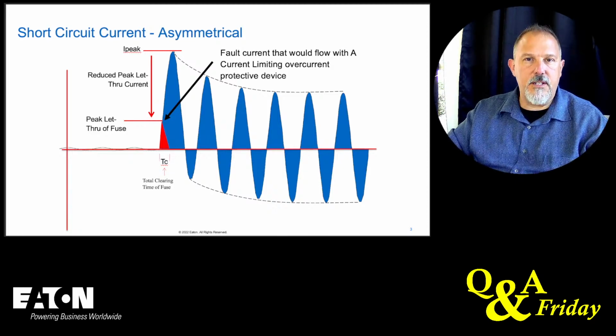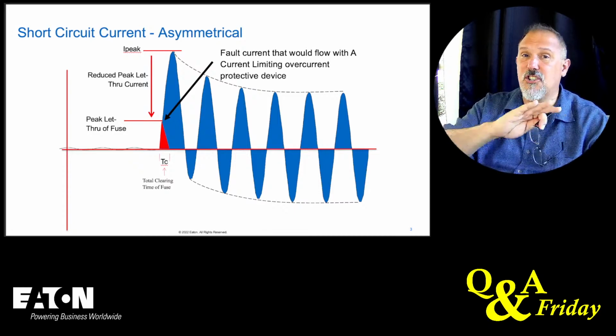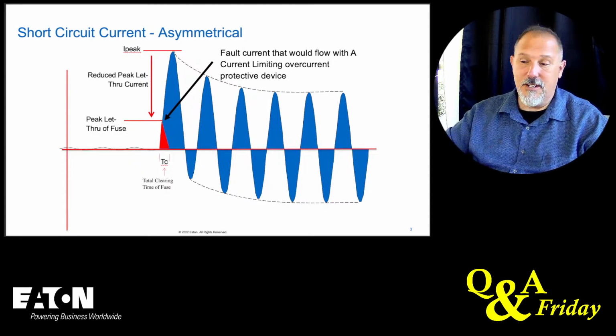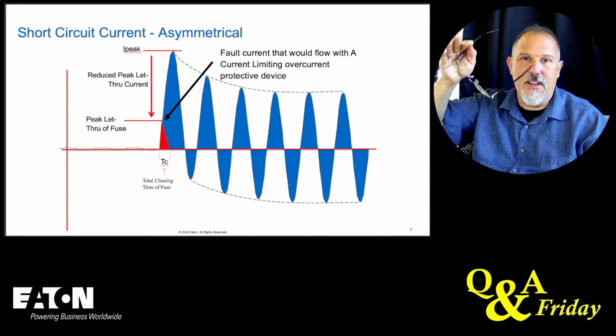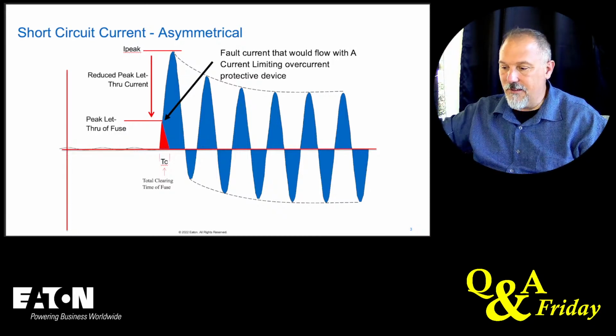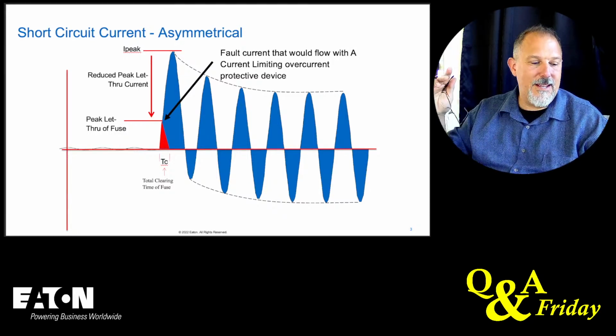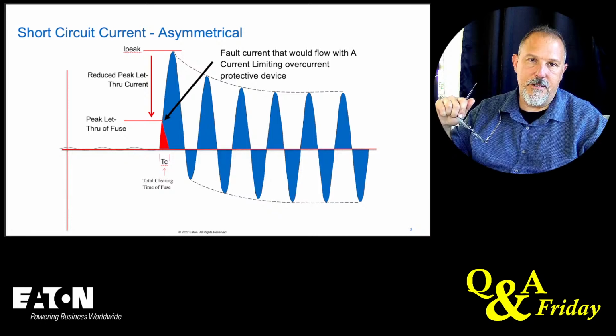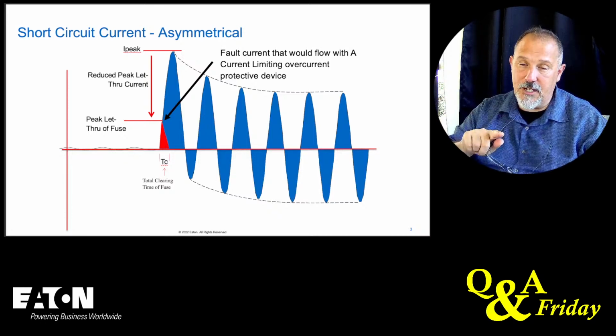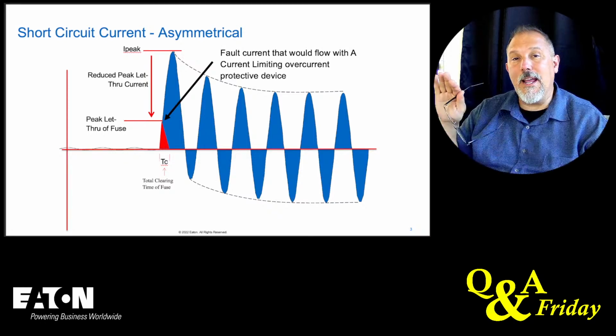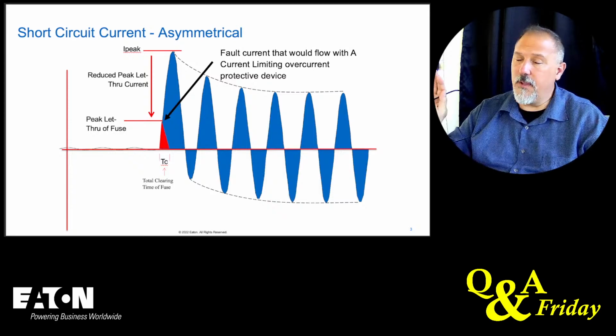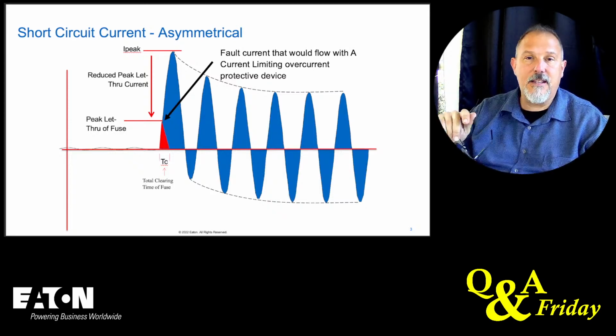A current limiting device has to have a clearing time faster than 0.0083. That would be a half a cycle. That has to stop completely the flow of current, which means you have to cut the peak off, and that tail that comes down has to clear in less than 0.0083 seconds. Now, knowing that information, then you start looking at trip curves, whether it be a fuse or a circuit breaker, and that tells you whether or not an overcurrent protective device is current limiting.